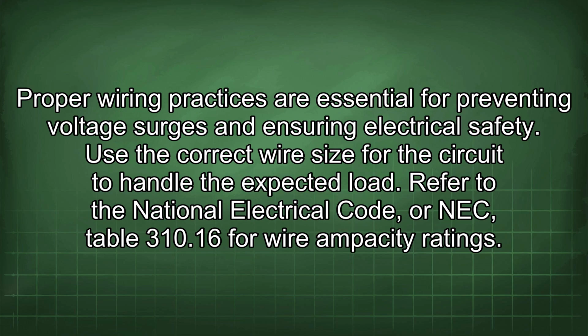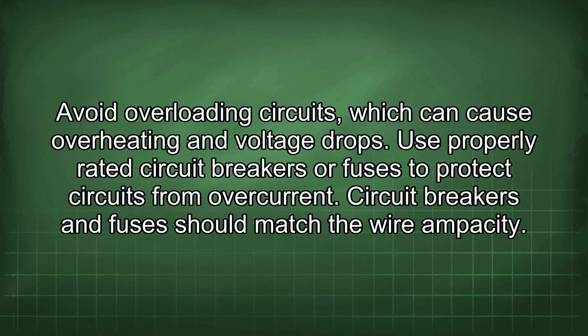Proper wiring practices are essential for preventing voltage surges and ensuring electrical safety. Use the correct wire size for the circuit to handle the expected load. Refer to the National Electrical Code, or NEC, Table 310.16 for wire ampacity ratings. Avoid overloading circuits, which can cause overheating and voltage drops.